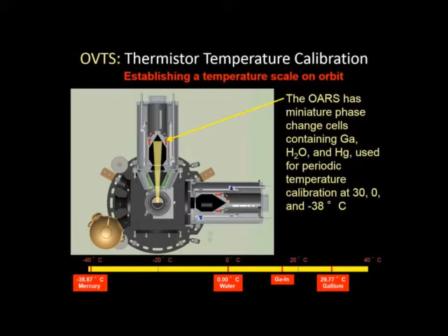And the features of the OARS, the two significant ones are, one, it contains 3 independent phase change cells containing gallium, water, and mercury, which we use, we determine their melt points and measure their melt points on orbit to set a temperature scale. Okay, so we use those to establish a temperature scale. And the other thing that we have to do is we have to be able to measure emissivity. And for that, we use this heated halo.